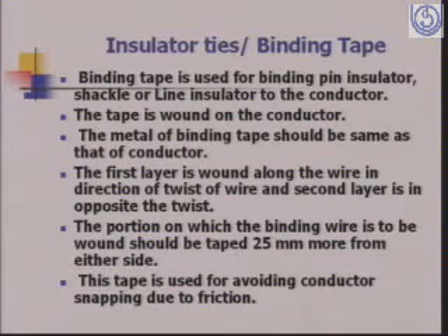And the first layer is wound along the wire in direction of twist of wire, and the second layer is in opposition to the twist. The portion on which the binding wire is to be wound should be taped 25 mm more from either side. This tape is used for avoiding conductor snapping due to friction. Otherwise, when the insulator is put on the conductor, then there will be friction.